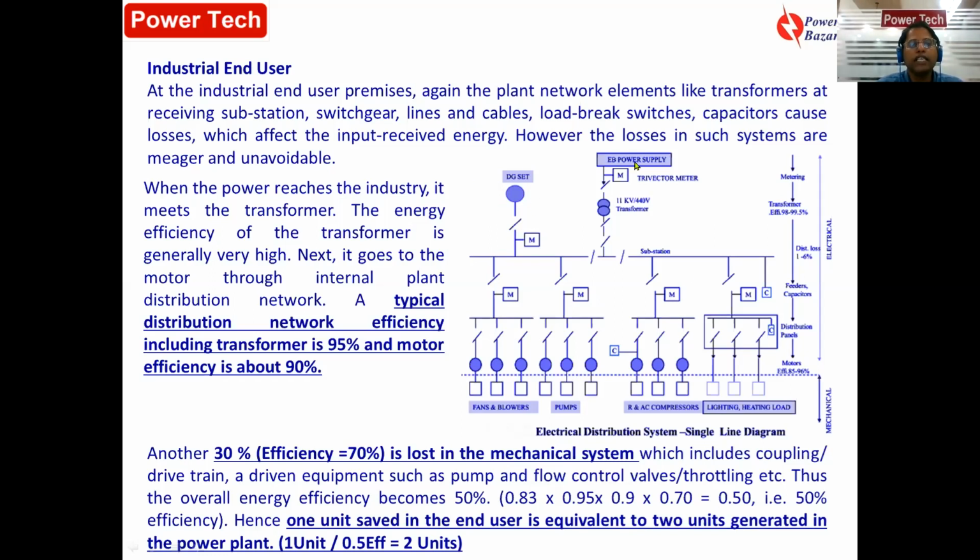Now you see here there is another one, the DG set. In case there is a power failure, this DG set will be able to run the total electrical supply by starting, and there is an isolation circuit. So if the DG set is operating, you should not operate the electrical power supply. If electrical power supply is available, we should not operate the DG set.